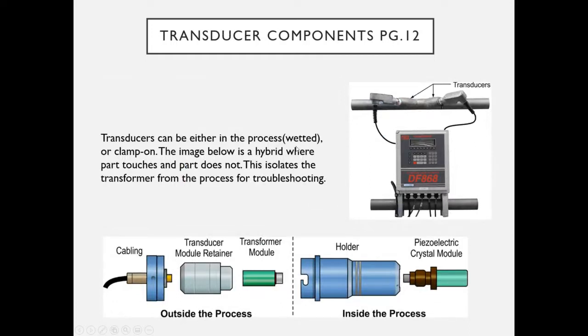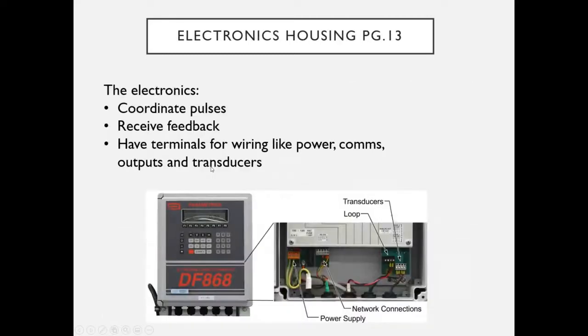Transducers can either be in-process (wetted, touching the process) or clamp-on (on the outside of the pipe). There is also a hybrid configuration where a holder is permanently and wetted to the piping system while the transducer module and cabling are quick-connected for easy servicing. The electronics housing coordinates pulses and input signals, receives feedback from sensors, and contains terminals, displays, and all communications, power output, and configuration functions.